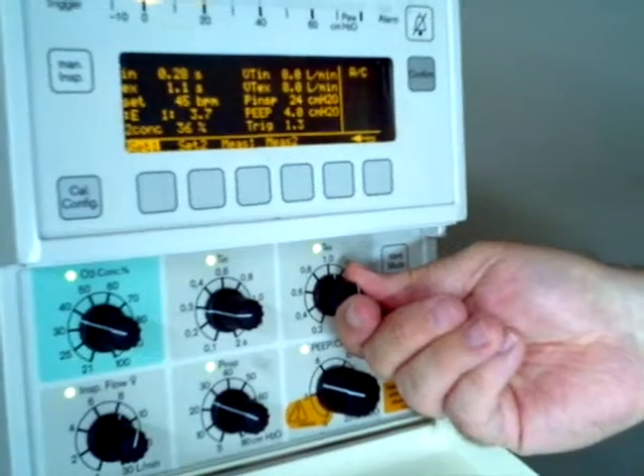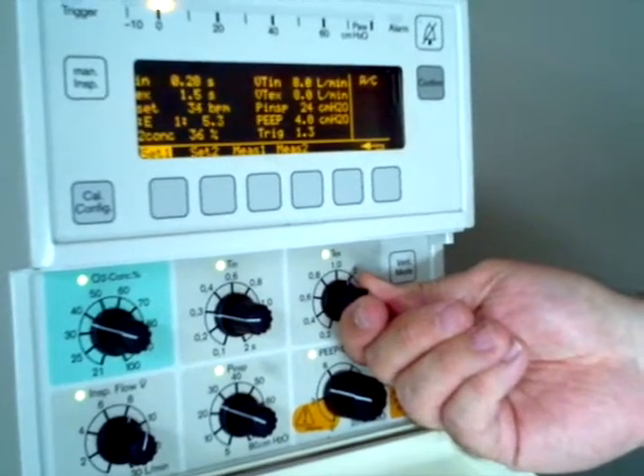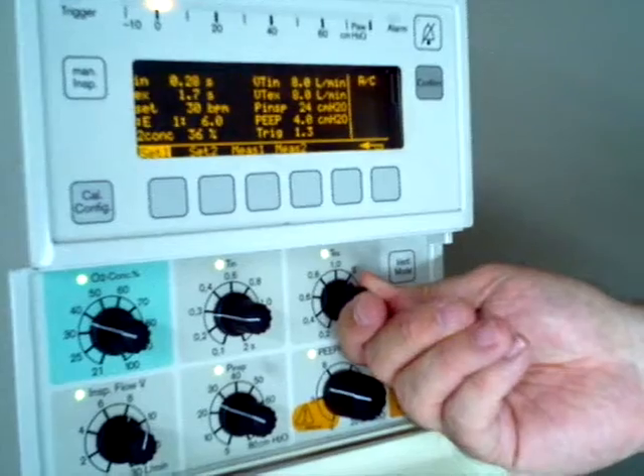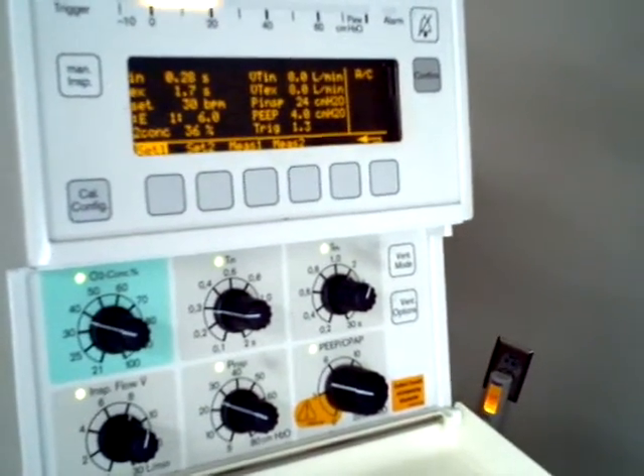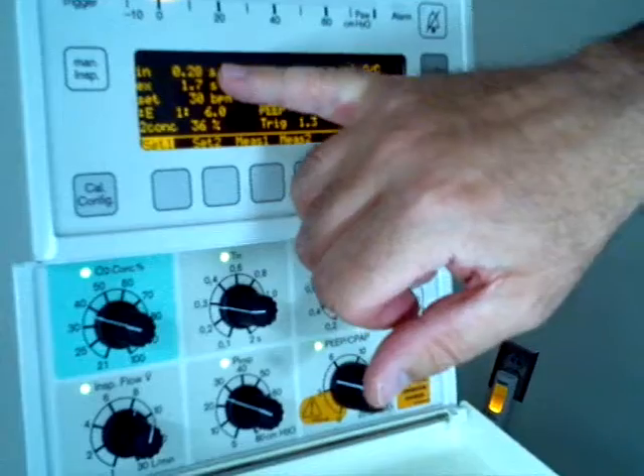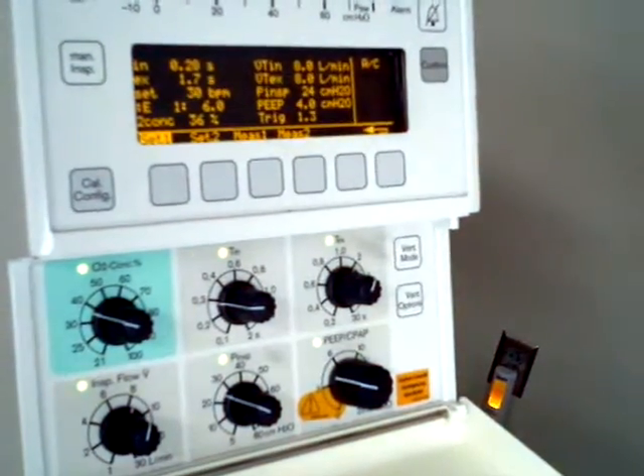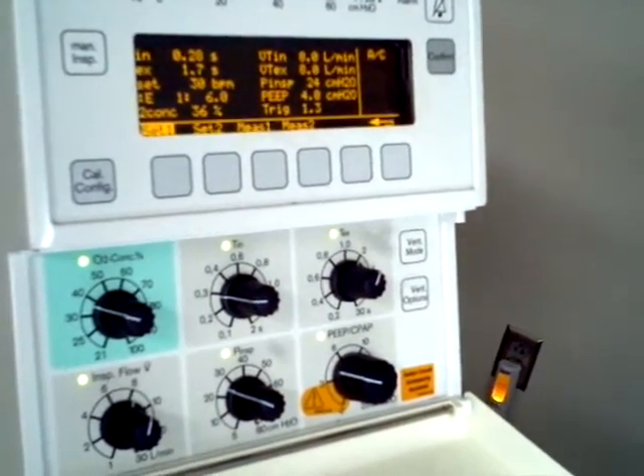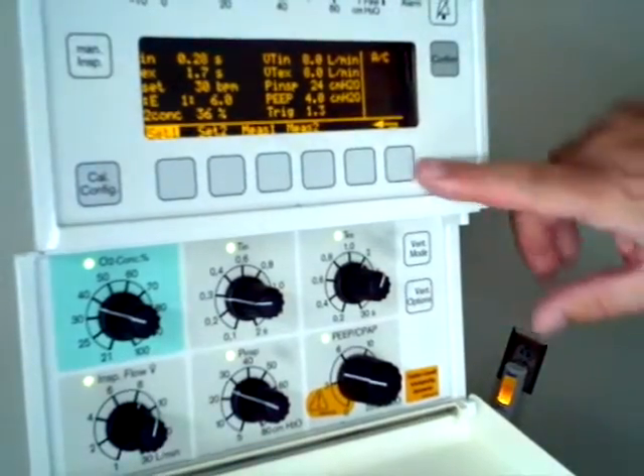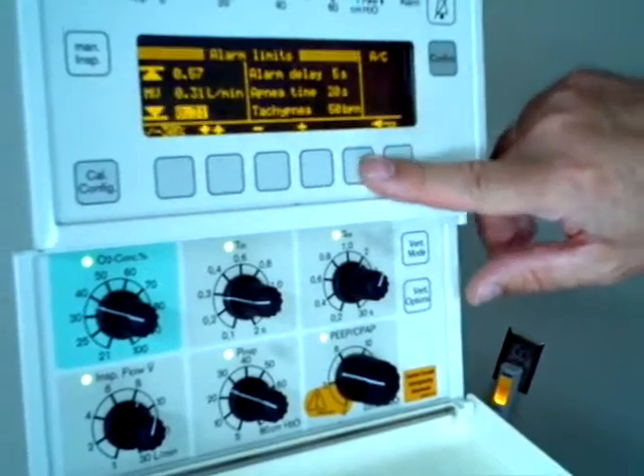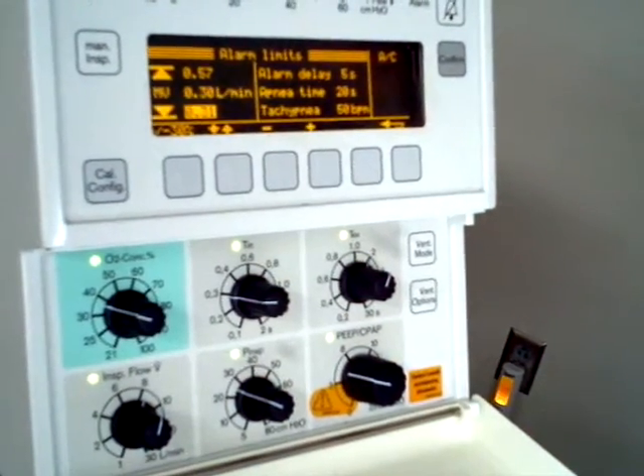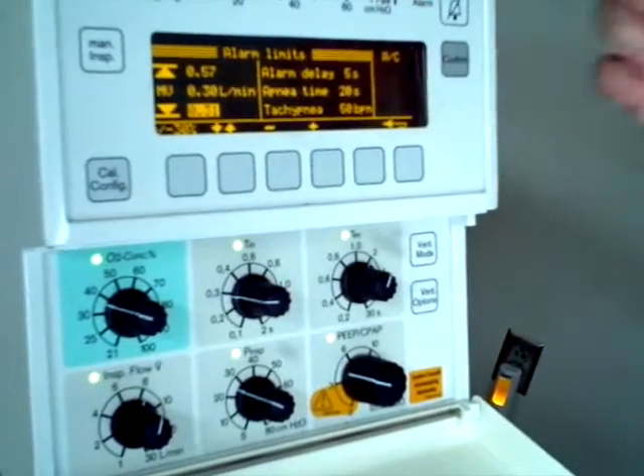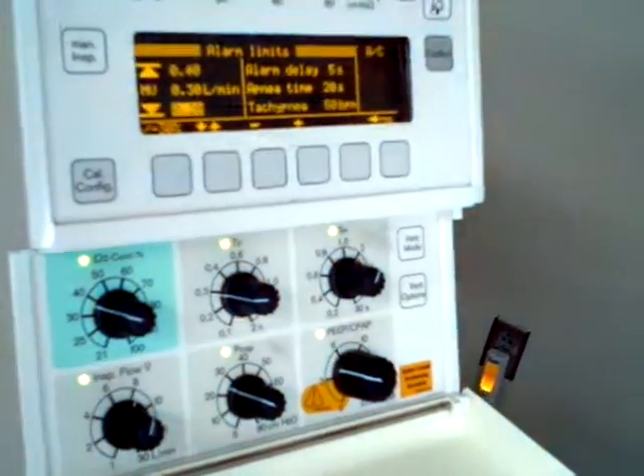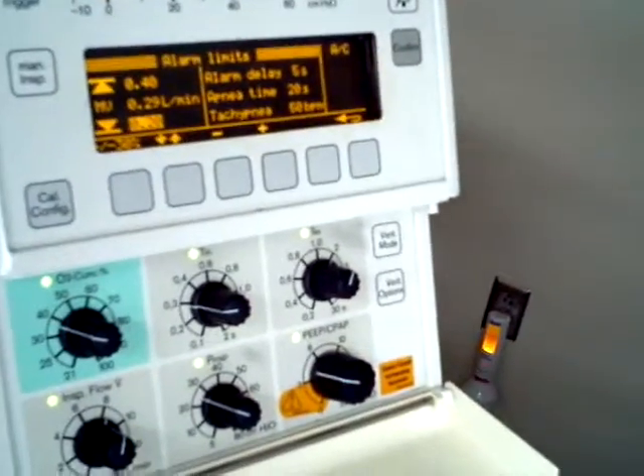Let's pull up our settings screen. And again, we're going to go down to 30. That looks like about 30 to me. If we look at our numbers, I ended up with 0.28, and I have an expiratory time of 1.7. That's pretty close to my 2-second total cycle time. All right. Go back. If I look at my minute volume, I'm going lower than my alarm, and I was going to say in about 5 seconds I'm going to get my alarm. So let's reset that. Now I have some better alarm settings for that particular minute volume.